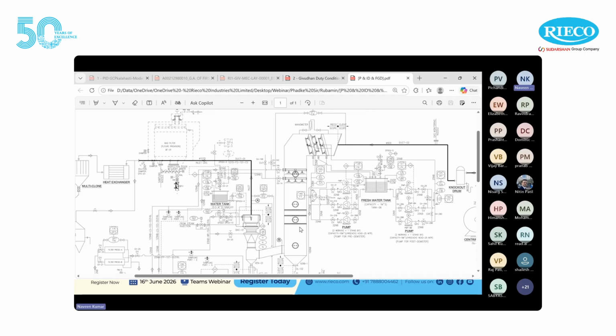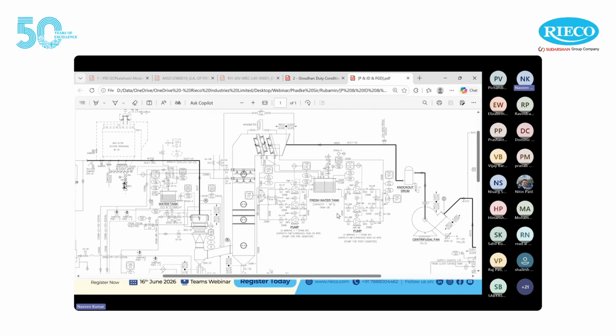At the end of the gas absorber at the top, we can see mist eliminators for taking care of the vapor droplets. Below the mist eliminators, we can see the spray banks from where the lime slurry is sprayed in the gas absorber. Below the spray banks we have what we call pipe decks, which are basically used to straighten out the gas which enters the gas absorber and ensure a uniform distribution inside the cross section of the gas absorber. It also plays a role in enhancing the neutralization of sulfur dioxide.